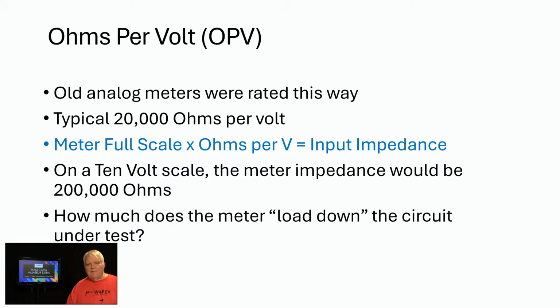And what that means is that if I was on the 10 volt scale, full scale, 10 volts, and it's 20,000 ohms per volt, then the meter's impedance would be 200,000 ohms. It'd be the equivalent of putting a 200,000 ohm resistor across the circuit that you're trying to test. That was important, especially back in the day of vacuum tubes, because vacuum tubes could be thrown off by a resistance that seems fairly high, but it's not.